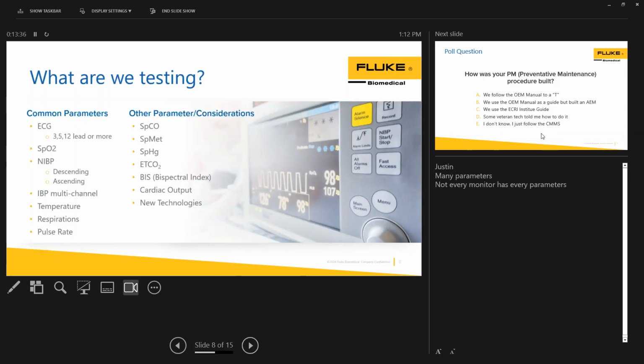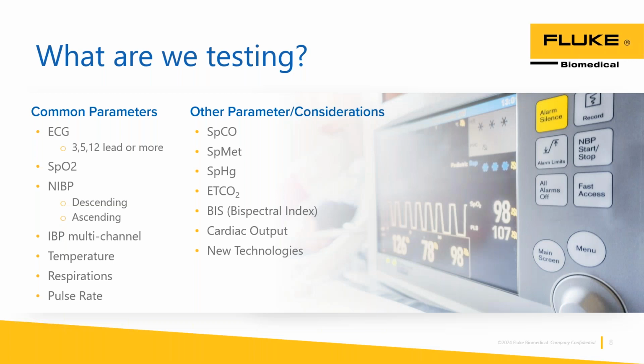Not a big deal. So let's talk about these different parameters while we work through this, because we're in a technology-based company, and that's when technology bites us. So let's talk about some of these common parameters you may or may not see on a patient monitor. We're all familiar with the ECG, but is it 3-lead, 5-lead, or 12-lead ECG? And just because your monitor has a 3-lead or 5-lead, is it capable of testing all 12 leads? Do we know if it's capable? Some examples might be the patient monitor built into defibrillators. Some of them have an option for a 12-lead ECG. Some I've even seen or heard of that have more than 12 leads.